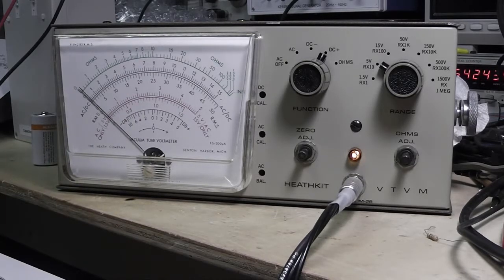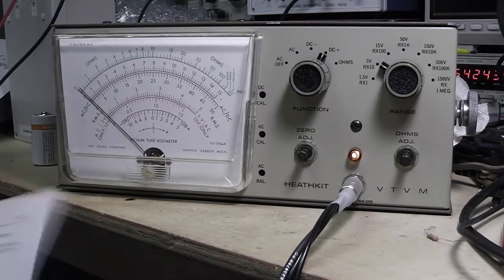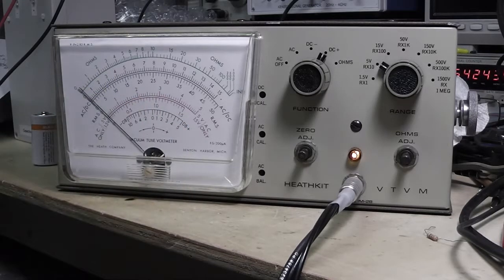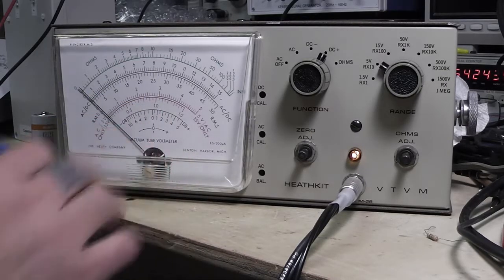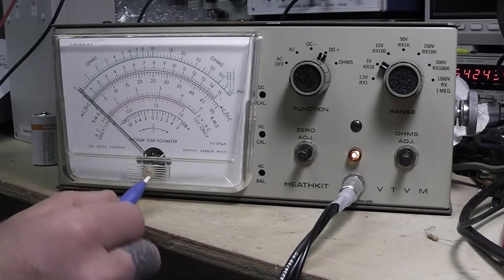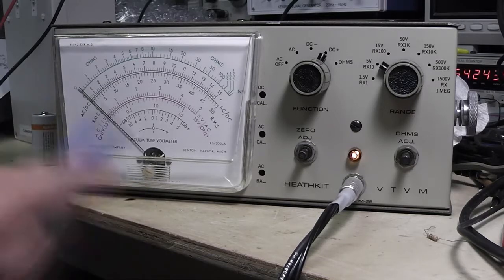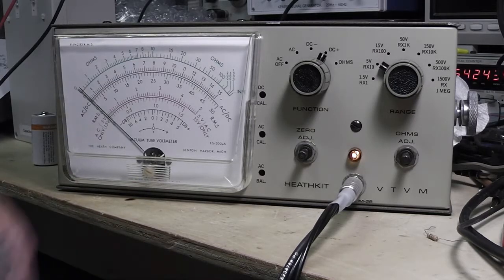Then you can plug it up, and if you have issues with the needle being up here, or something looks weird, take a dryer sheet, like a Bounce dryer sheet, and run it over the face of the meter, because this will build up static sometimes. Discharge any of that static, and make sure it comes back down over here on the left hand side. Then adjust that, because you don't want to adjust it with a charge on it, it'll be fighting it. So get that right on the 0, adjusted. Then you can plug it in, turn it on, let it warm up 2 or 3 hours, whatever. Okay, so let's start the procedure from there.